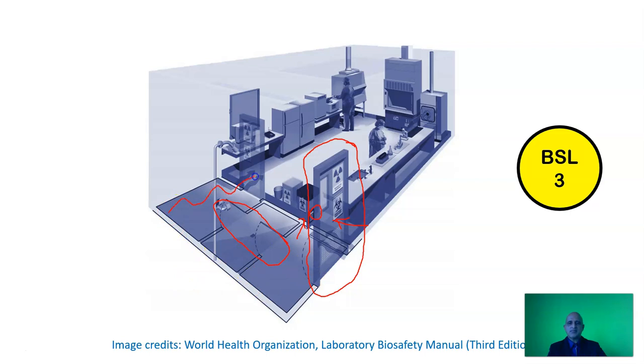One can note that there is directional airflow as described earlier and this facility is maintained at negative pressure with reference to the external environment. Note that the biological safety cabinets and fume hood are at the far end of the facility and the autoclave has been shifted into the facility itself. All of this equipment is hard ducted into the system and the exhaust vents out via HEPA filters.